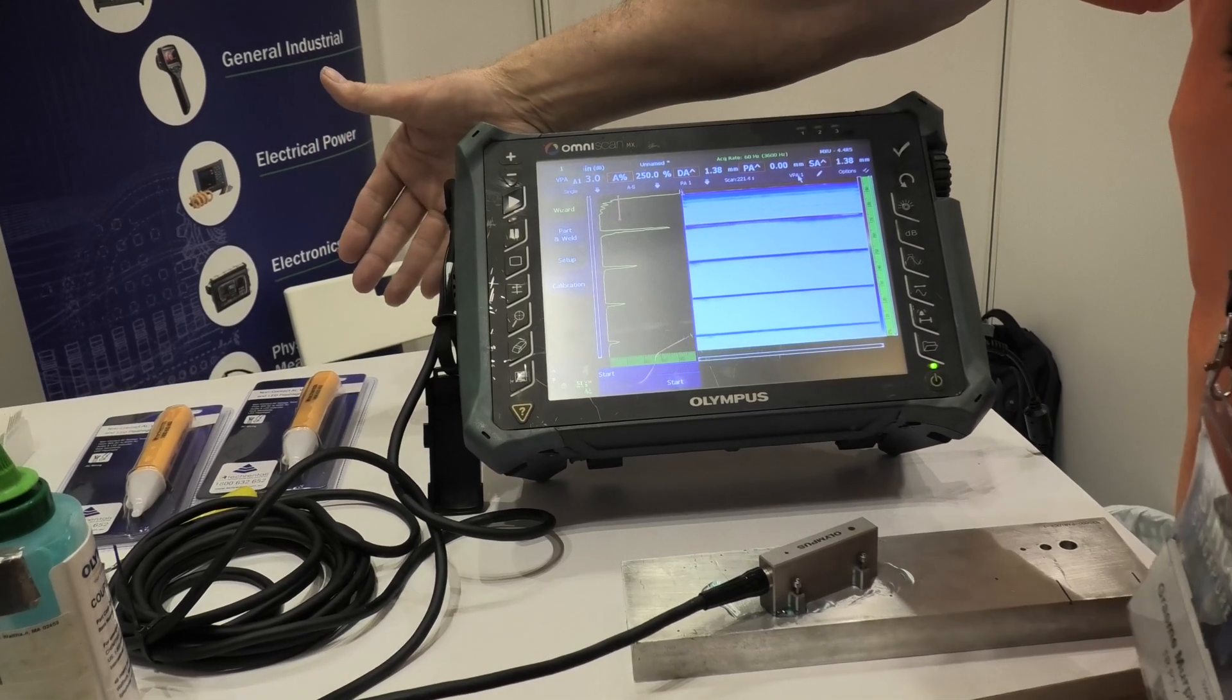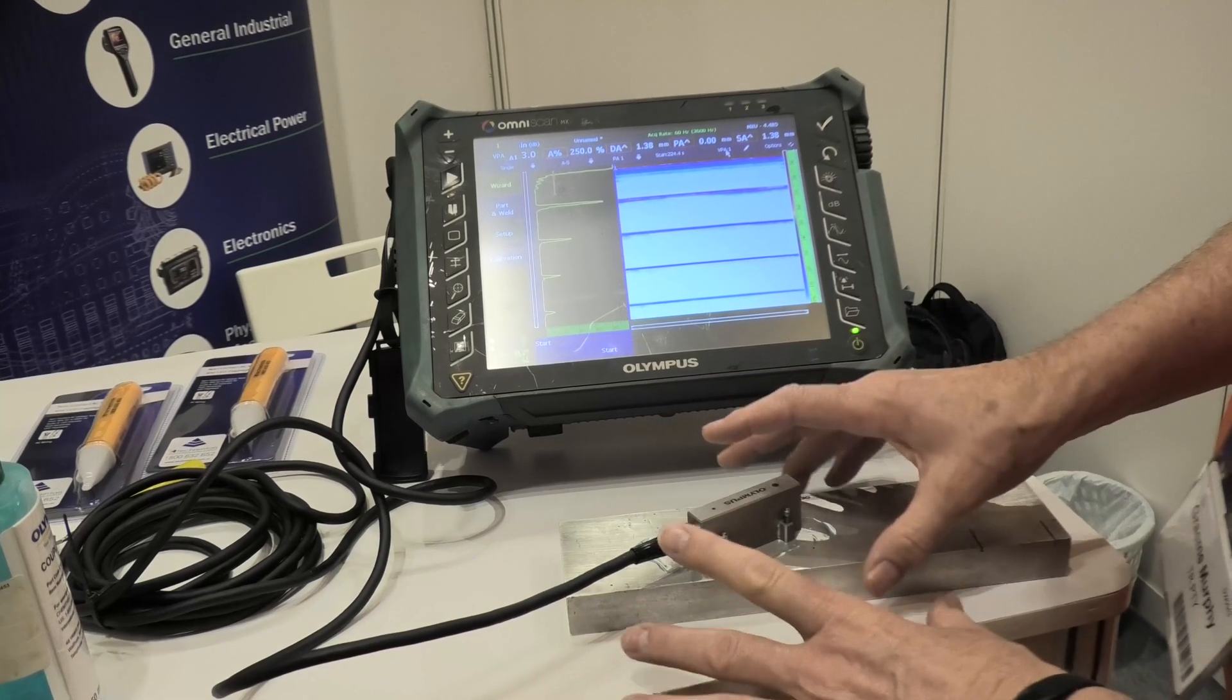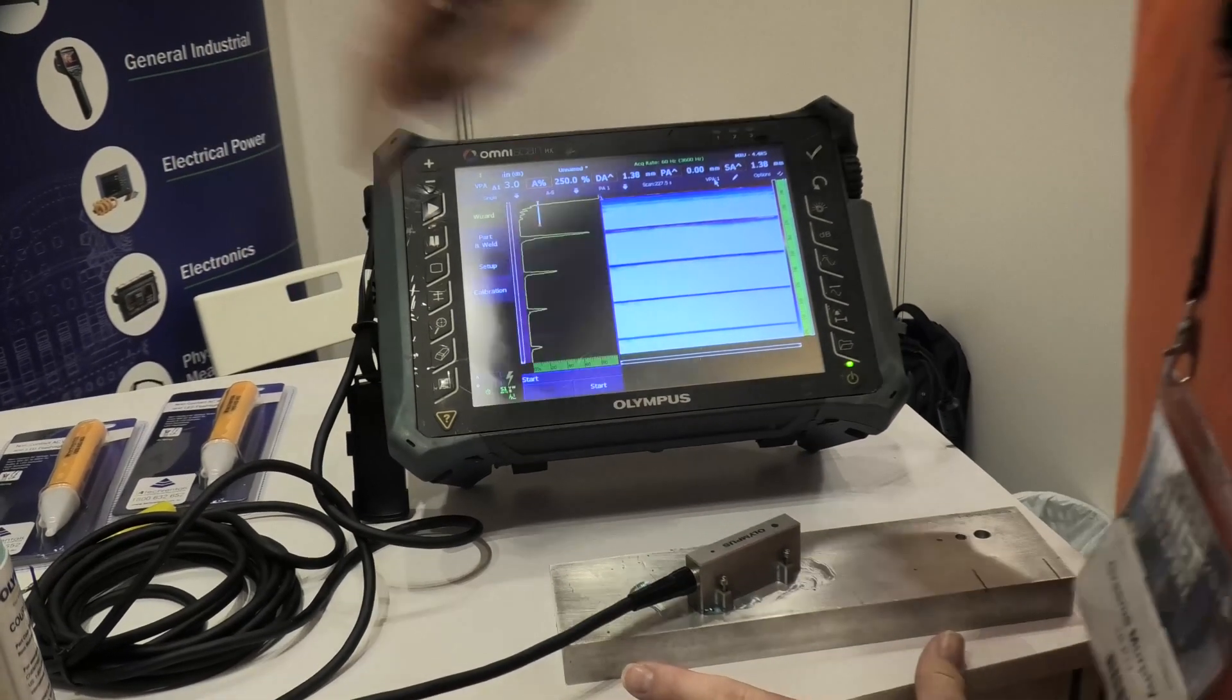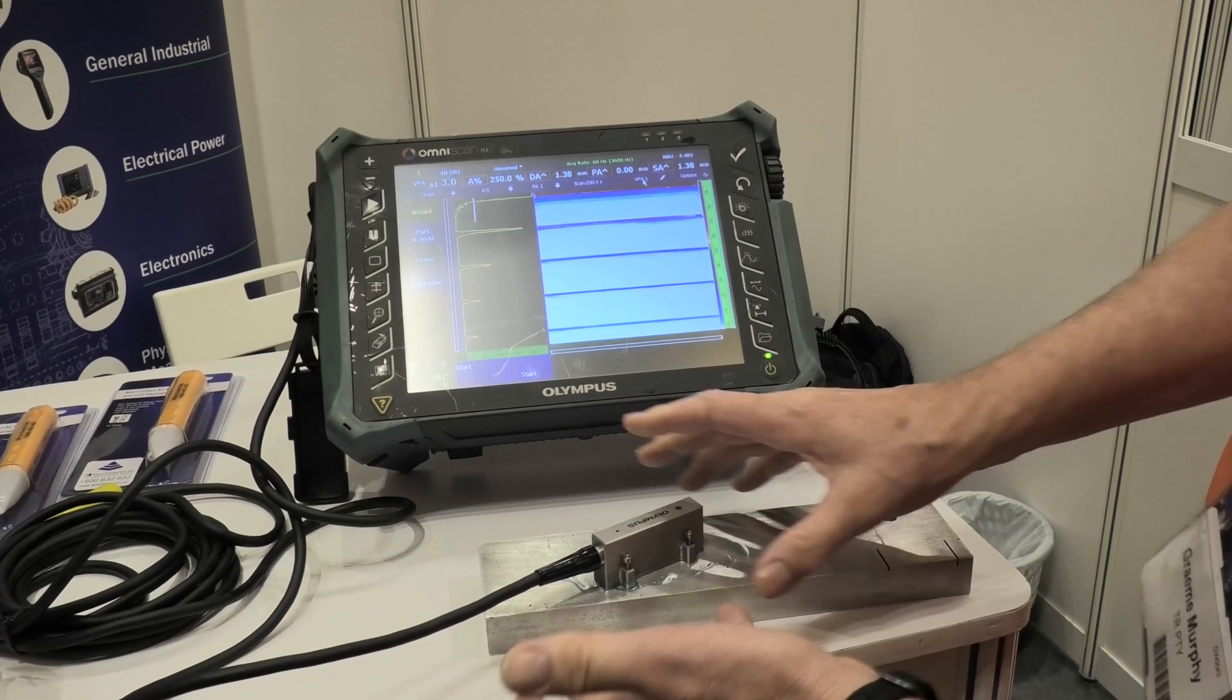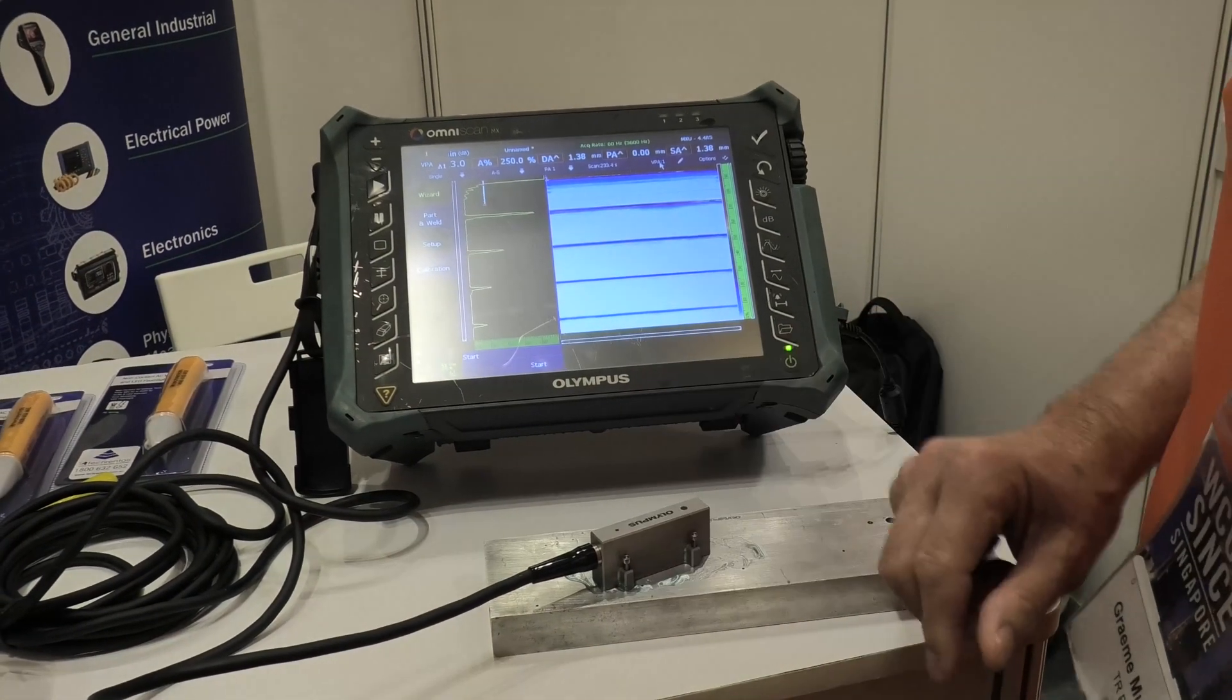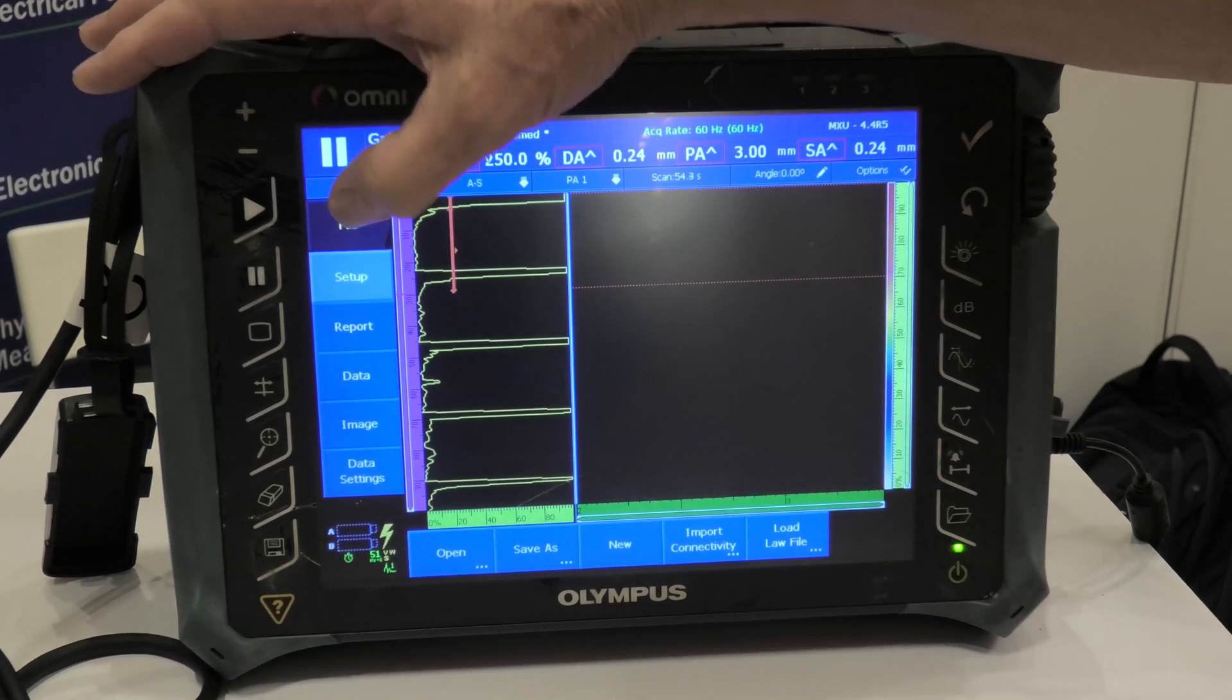We're going to check this probe out. We're going to make sure all the elements on the probe are working properly. I've plugged the probe in and I've got it on a reference piece, just a piece of metal of a known thickness with an appropriate couplant. Okay, we've powered the instrument up.